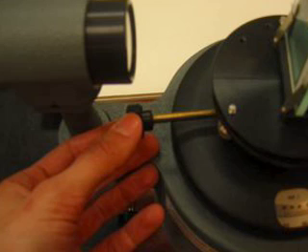If your table is badly misaligned, begin by loosening the grating table screw. Then turn the table slightly so that the grating is perpendicular to the light leaving the collimator. Then repeat the three angle measurements and check if the alignment has improved.